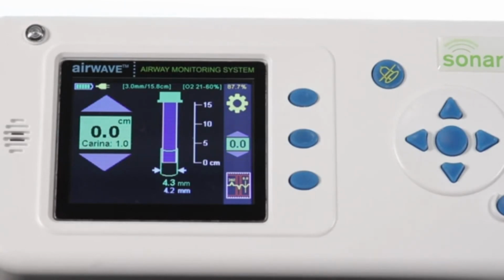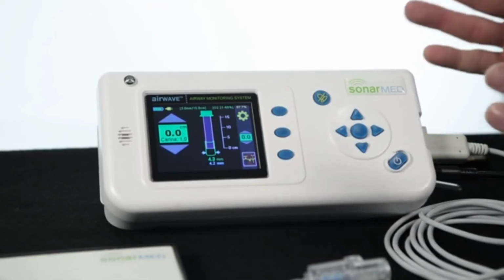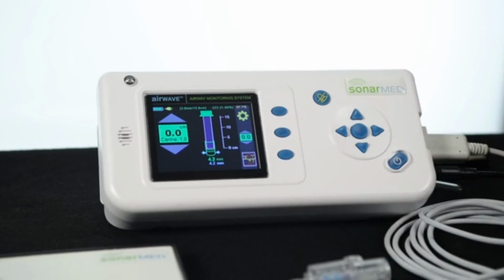So again, in the SonarMed airwave monitoring system, after you're calibrated, you can set the carina distance by manually entering what that distance is after you've measured it off of a post-intubation chest x-ray, and you can modify the length of the endotracheal tube if for some reason your unit chooses to cut the length of the tube so that the monitor knows exactly how long of a tube it's sending the signal through.